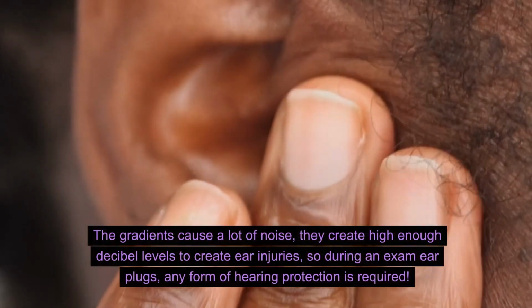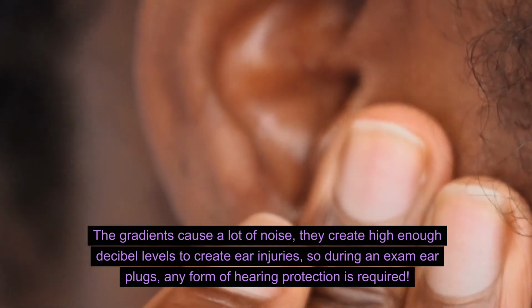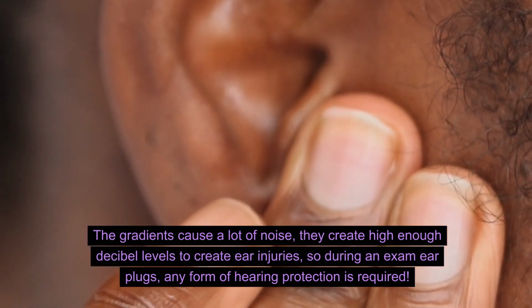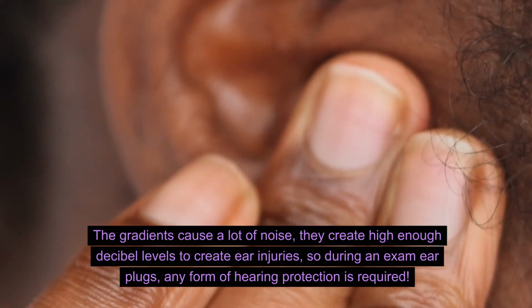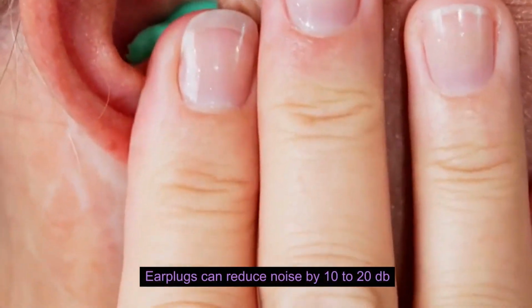The gradients cause a lot of noise. They create high enough decibel levels to cause ear injuries. So during an exam, earplugs or any form of hearing protection is required. Earplugs can reduce noise by 10 to 20 dB.